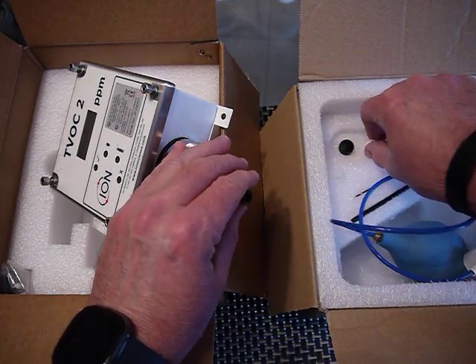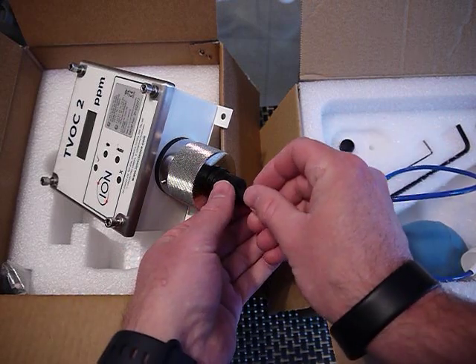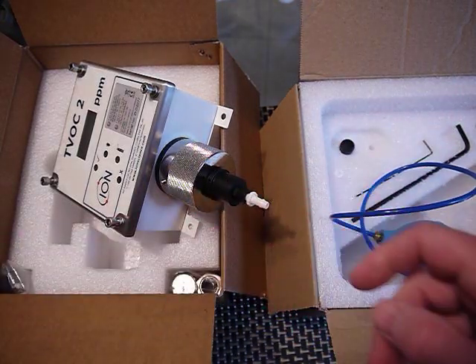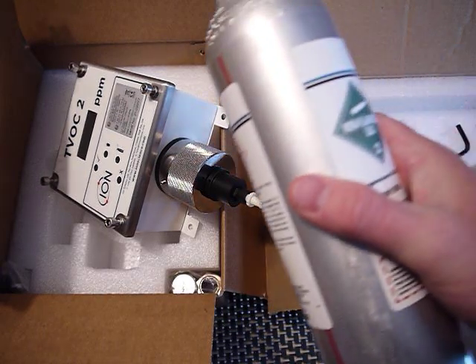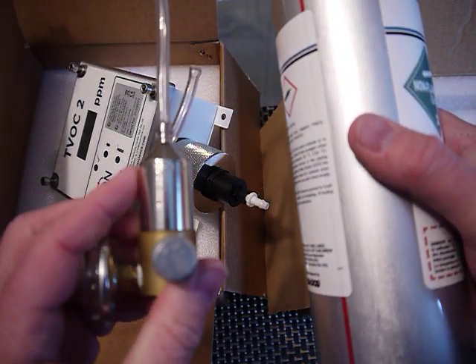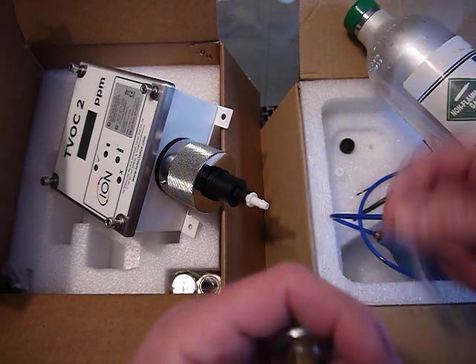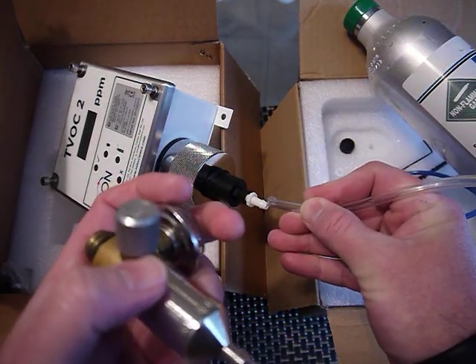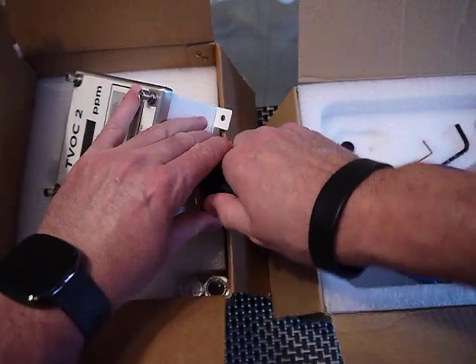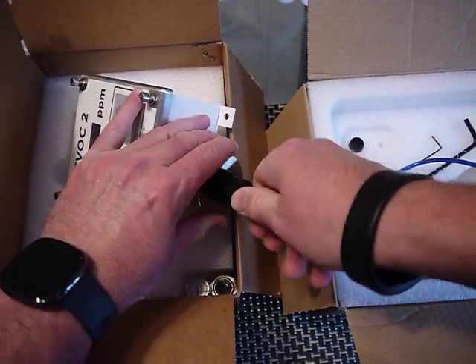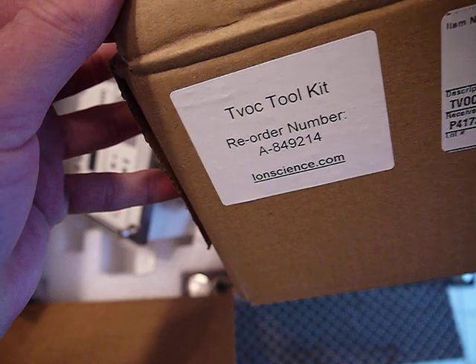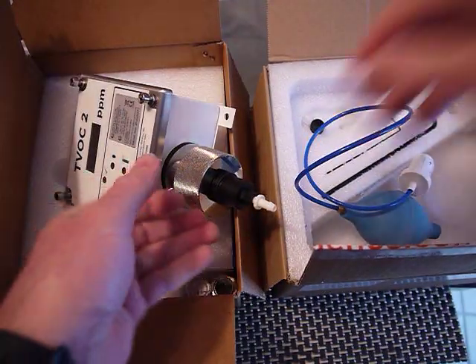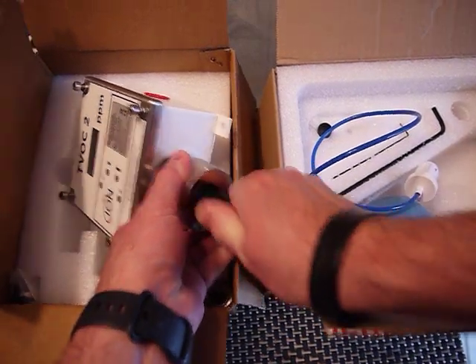And then if I want to introduce calibration gas, for example, this unit is set as a 0 to 1000 ppm unit, but we normally would use 100 ppm isobutylene and a manual regulator. So this regulator, once hooked up to the gas, would hook into this, and you could introduce your flow of span gas. These accessories here in this kit are part of this toolkit. So if you're ordering the unit, it's good to order this toolkit along with it, at least one kit if you're buying one or multiple of these units.